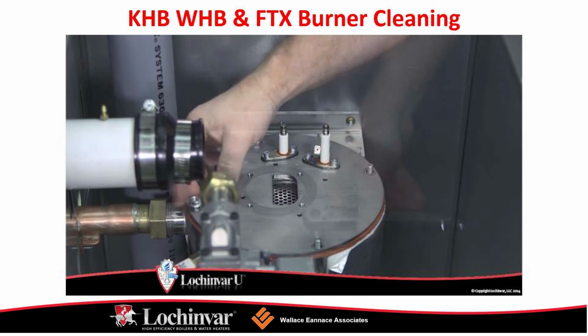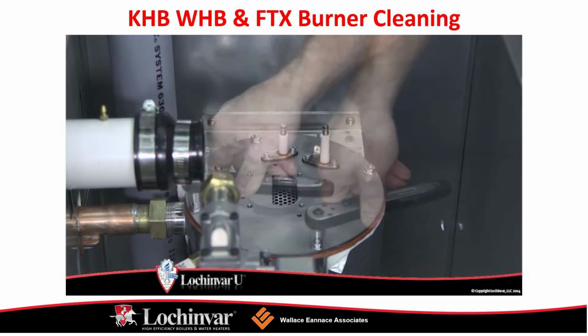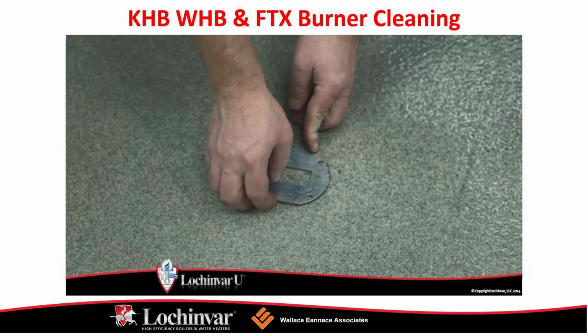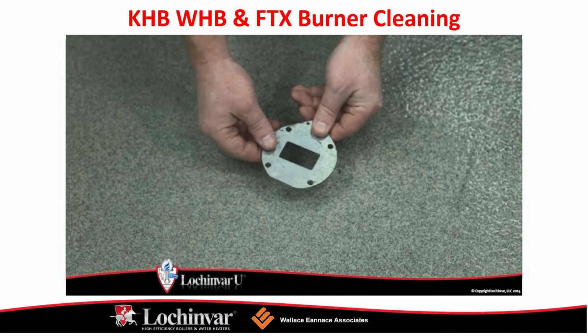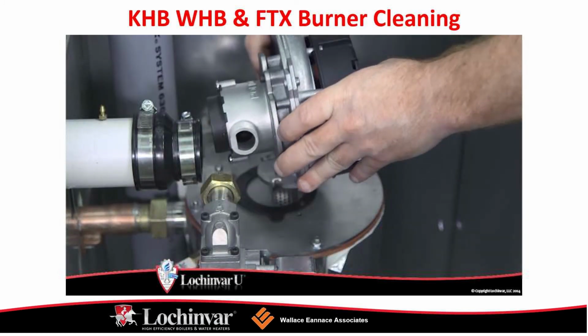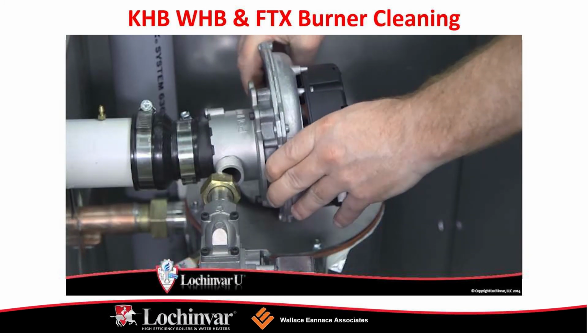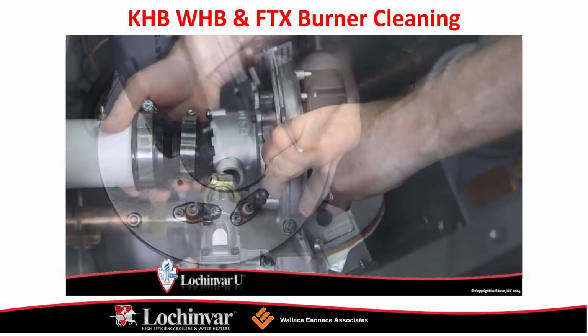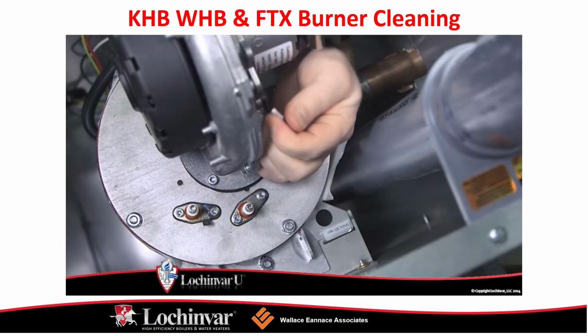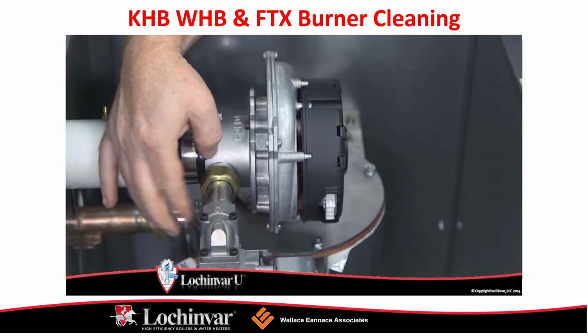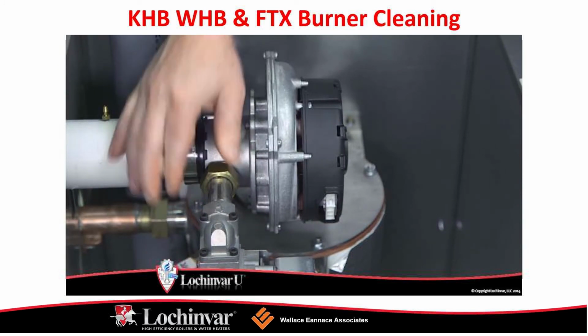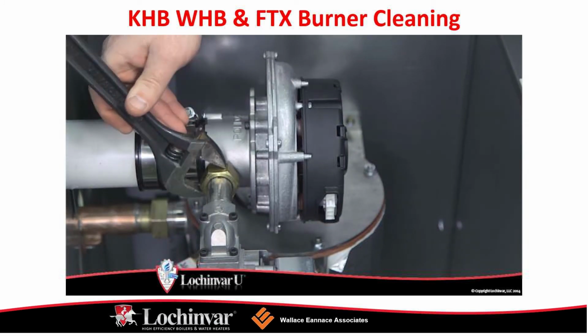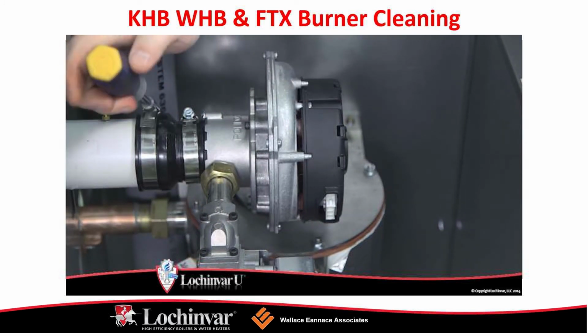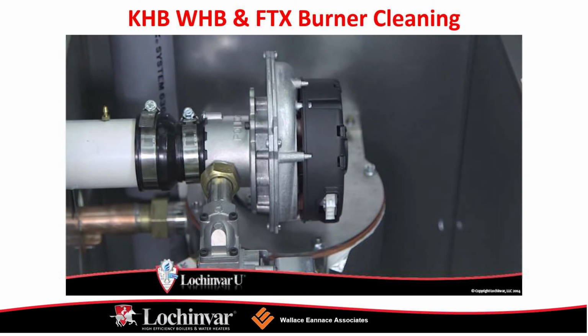If no damage is observed, clean the burner by using compressed air and a vacuum. The cleaning process will be slightly different based on the model. For models 55 through 85, use compressed air and a vacuum. For models 110 through 155, use compressed air. For models 199 through 285, use compressed air and a vacuum.